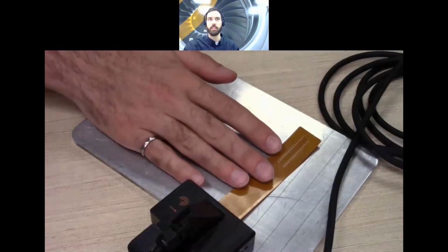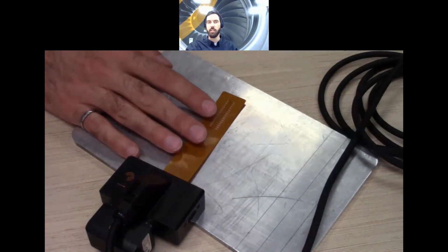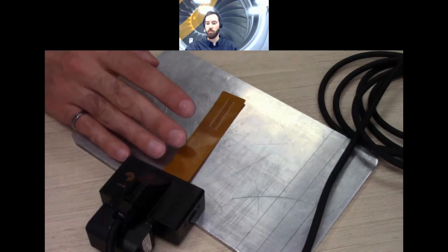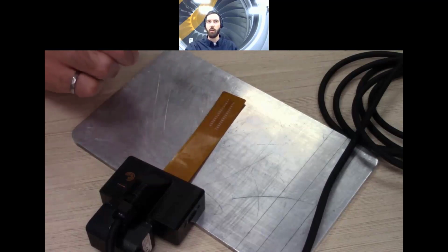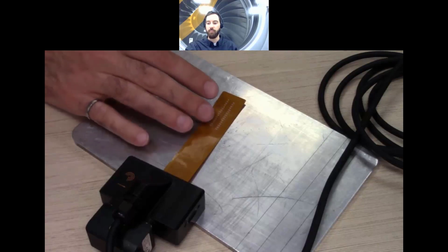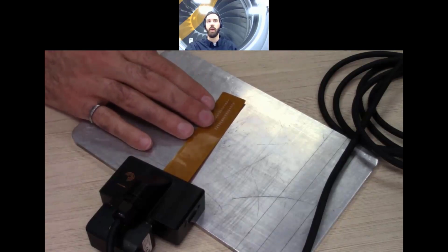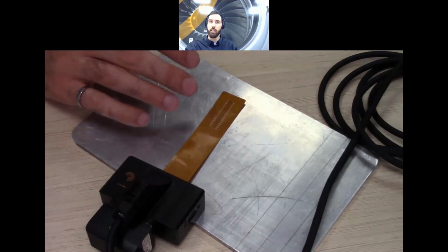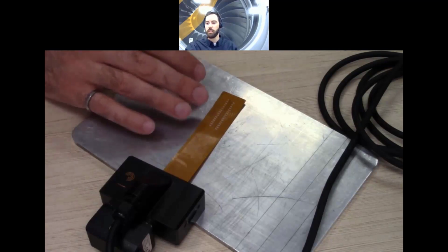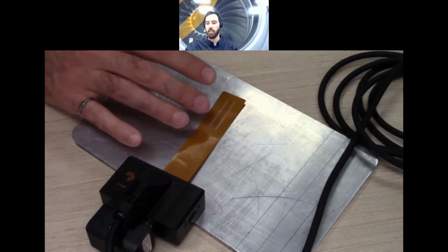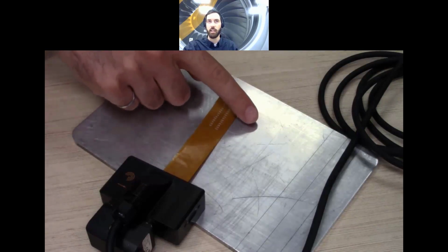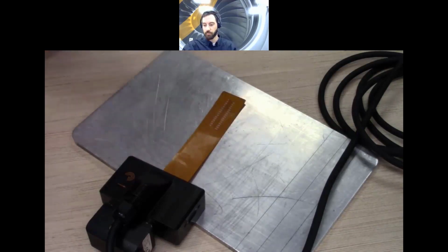One word on the frequency of those probes, because this is very important to consider. The flexible PFlex operate at very high frequency. This is one of the limitations of those printed coils. They operate in this case at 1500 kilohertz, which is very high. For surface breaking detection, this has no impact. This is the perfect tool to detect little indications like those that are breaking the surface.